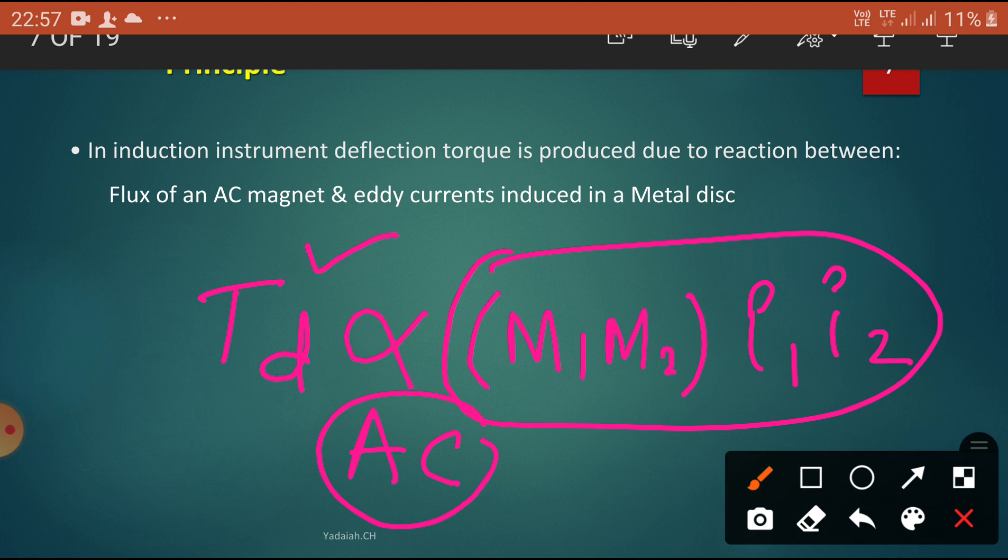The basic principle of the energy meter: when the energy meter is connected in the circuit, the current coil carries the load current, whereas the pressure coil carries the current proportional to the voltage because it is connected in parallel. The eddy currents are induced in the disc due to the flux established by the series and shunt magnet, causing a driving force which results in the disc rotating in the air gap. The braking torque is produced by the braking magnet, and by adjusting the position of this magnet, the desired speed per unit can be obtained.